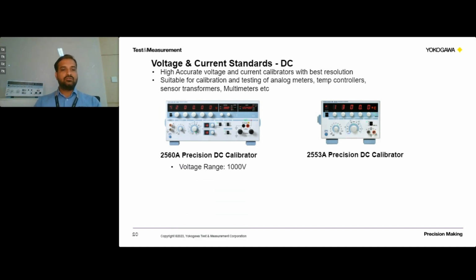Here also, the voltage range is up to 1000 volts, which is again a wide range, and the current range is up to 30 amps. With this calibrator, we will be able to cover voltage up to 1000 volts and current up to 30 amps. It also has the capability to source temperature parameters like RTDs and thermocouples, and resistance up to 400 ohms.